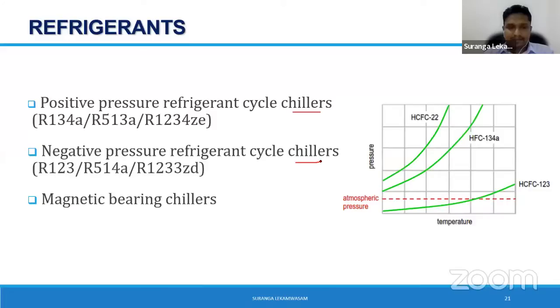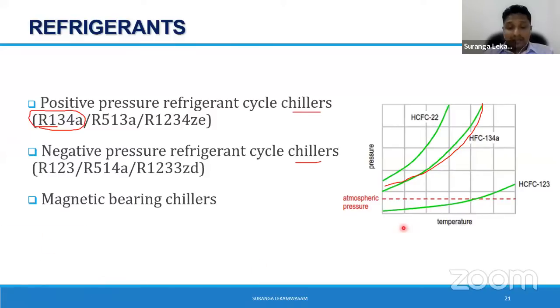What do you mean by that? Let's say you select the most commonly used refrigerant, R134A. Its condenser and evaporator, because if you get the chiller, it operates at two pressures, right? Evaporator pressure and condenser pressure. Both pressures are higher than the ambient pressure. You can see the curve shows this is my ambient. It's lower than both the operating pressures. So what happens if there is a leak in your heat exchanger? The refrigerant moves out. You can smell the refrigerant.